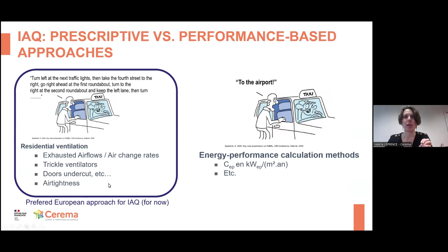The problem with the prescriptive approach is that you need good commissioning of the building at the end to make sure all those aspects are good, to guarantee good indoor air quality. Since we don't have performance targets for indoor quality, you need to check that the airtightness is good, that the ventilation provides the right flow rate, that door undercuts are made, etc., to make sure you will indeed have good indoor air quality in the building.